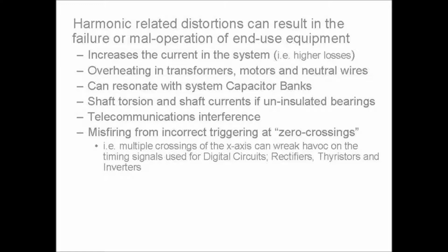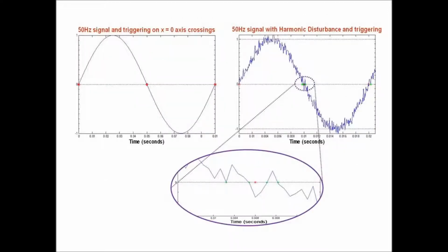Another thing I mentioned a few minutes ago is you can have shaft torsion brought on, and shaft currents if you don't have any bearings insulated properly, which can cause vibrations and basically break your motor or your generator. Telecoms interference has been much touted in the past. And then misfiring or incorrect triggering at zero crossings. I suppose the easiest way to talk about that is by demonstration.